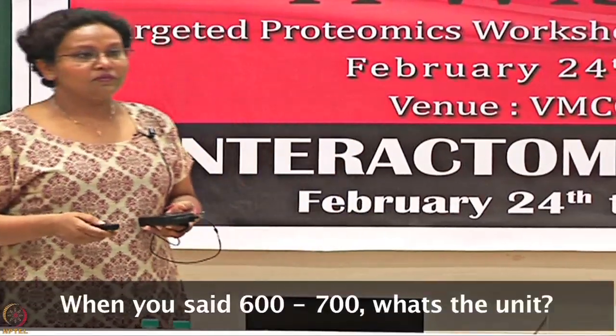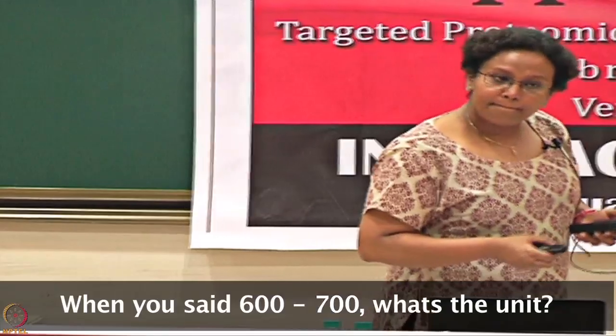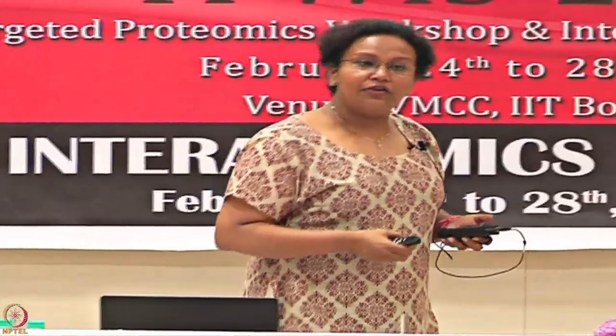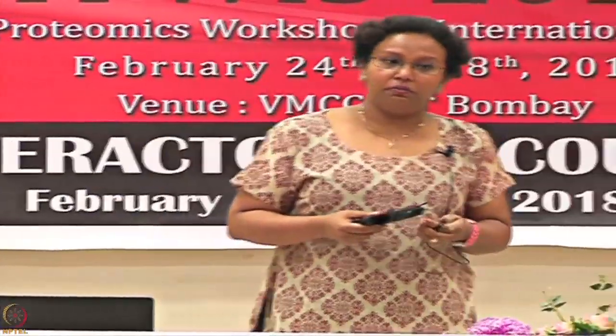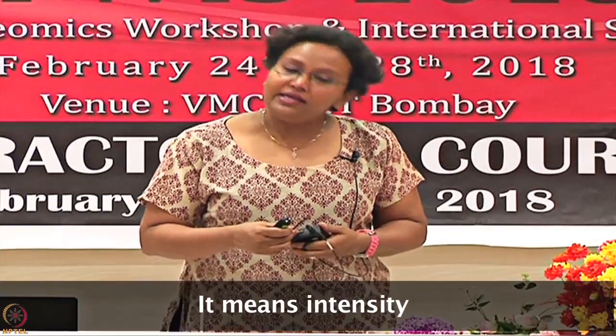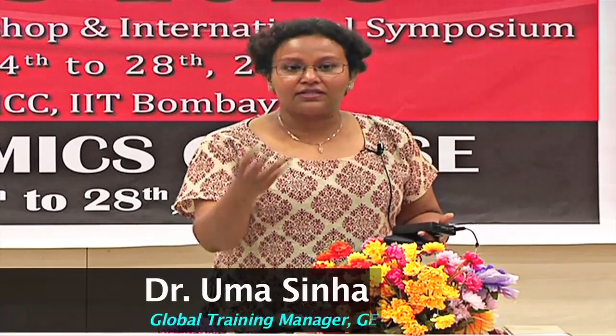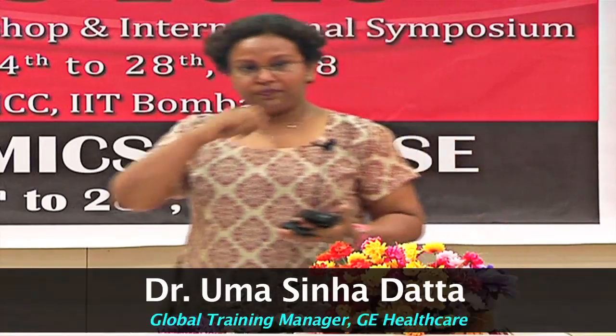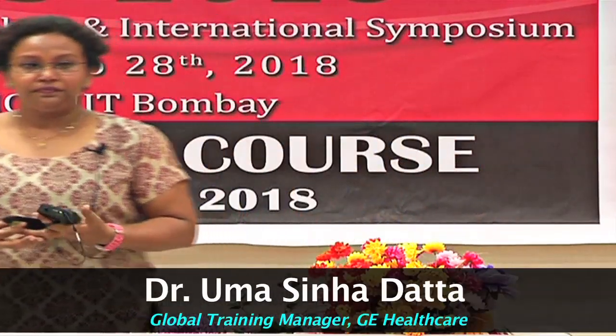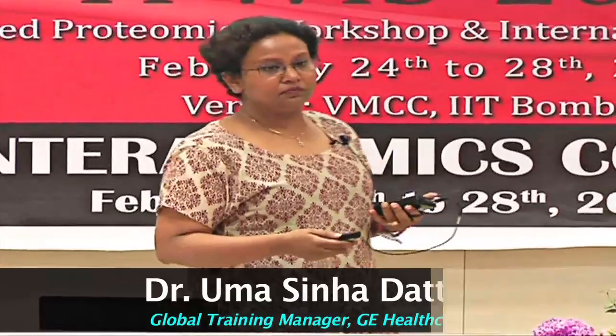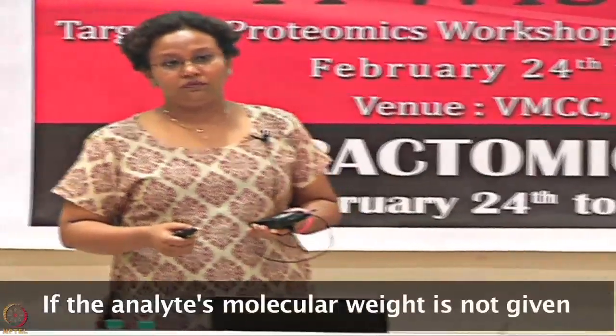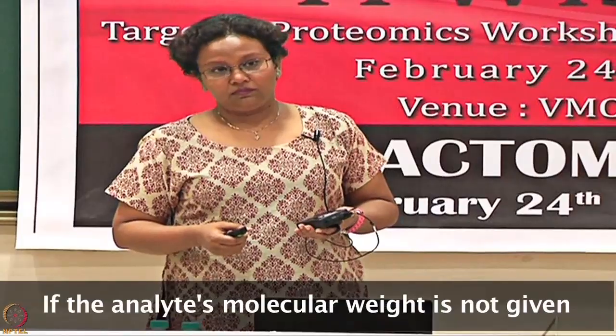Question: when you say 600-700, what's the unit? Answer: RU - resonance unit or response unit. The change in mass changes the refractive index, and that is related to your response unit.